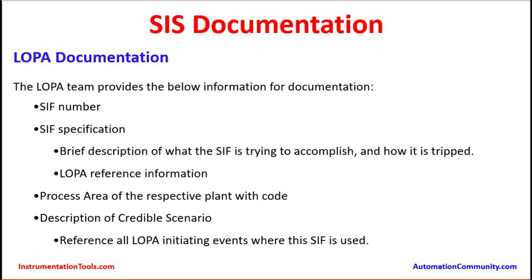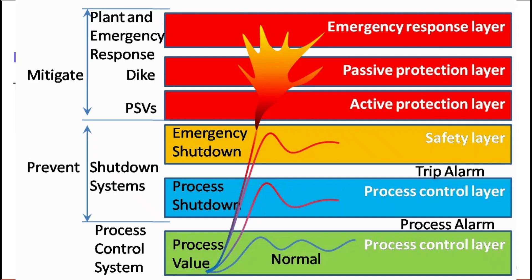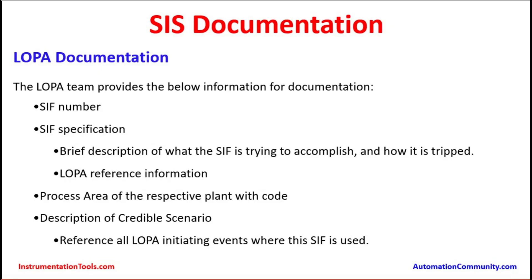SIS documentation involves different types of documentation. The first one is LOPA documentation. LOPA stands for Layer of Protection Analysis. The LOPA team provides the following information for documentation: the SIF number (Safety Instrumented Function number), SIF specification, a brief description of what the SIF is trying to accomplish, how it is tripped, what the intent is, and how the trip action is carried out.